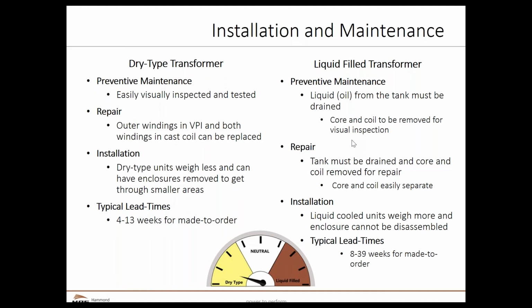When I go to liquid filled transformers, typically for preventive maintenance, because I can't directly visually inspect the transformers, I'm taking samples of the oil periodically and sending those in for testing. If for some reason I need to repair a core and coil issue, I will have to drain the tank. If a bushing starts to leak, I will probably have to drain the tank in order to fix that. So maintenance issues become much more intense and problematic. And again, I can't directly inspect the core and coil for damage.